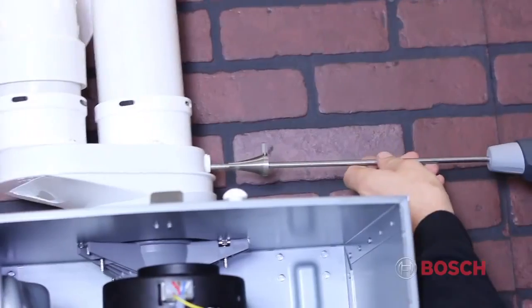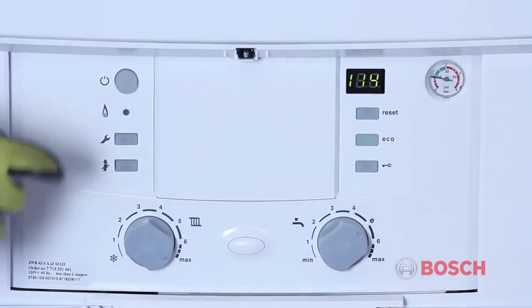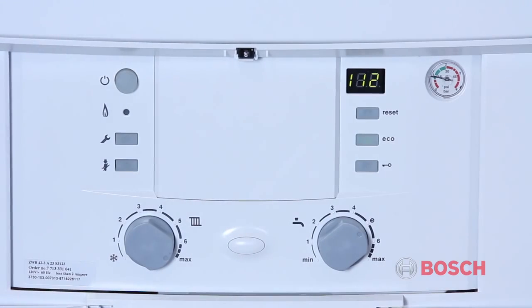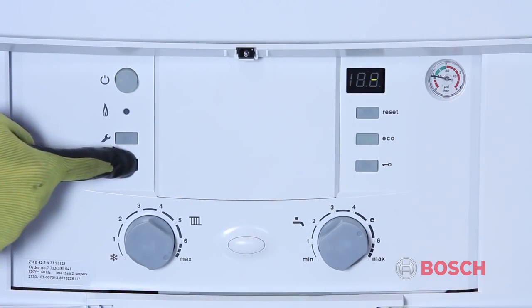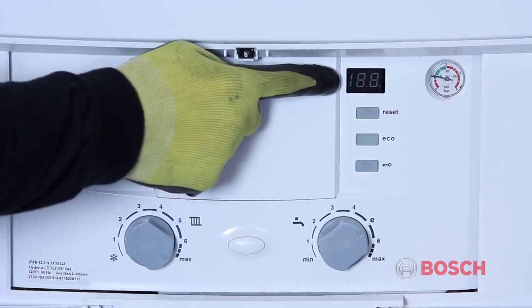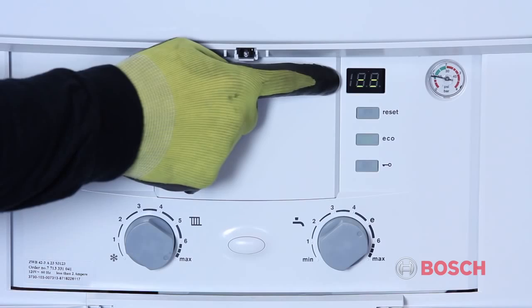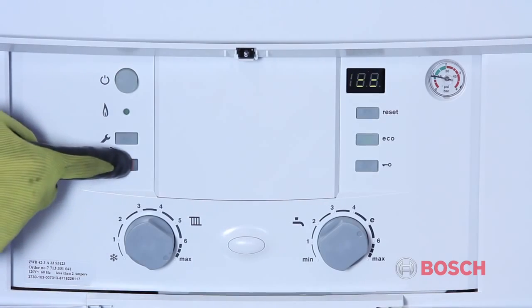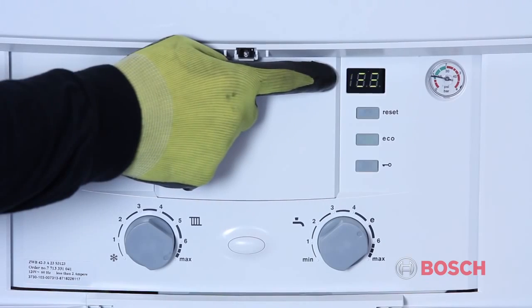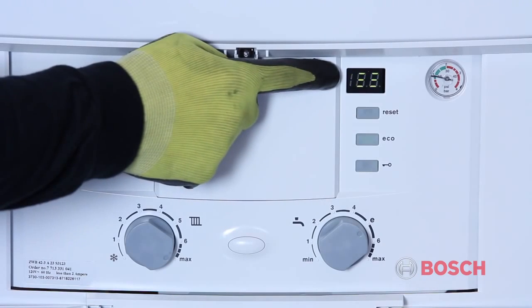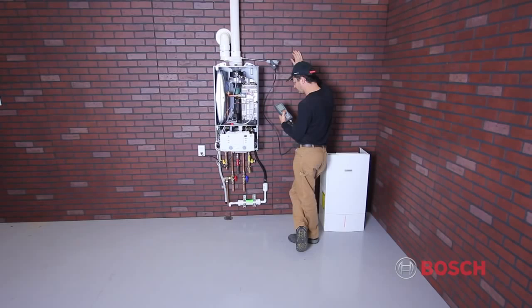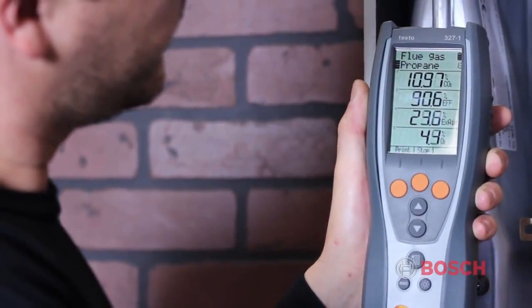Remove the supplied test plug from the flue. Insert the probe. To enter the chimney sweep or burner test mode, press and hold down this button for 5 seconds or more until the display changes. The display will change to 2 sets of dashes. These dashes will alternate with the current boiler temperature. To get into high fire mode for combustion testing, press and release the chimney sweep button 1 time. Watch your meter for changes in combustion and allow the readings to stabilize.